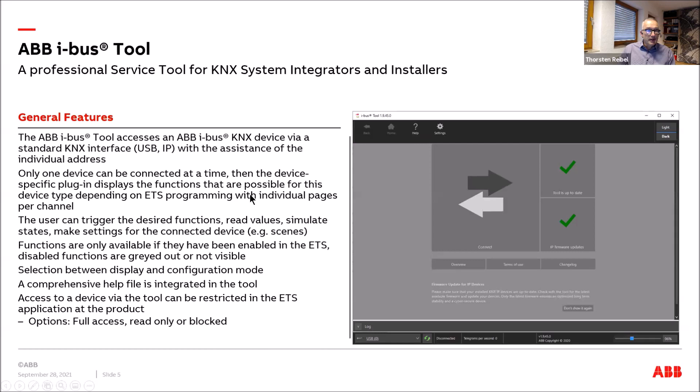From the tool you can trigger functions, read values, simulate states, and make settings — for example, store a new scene if available. These functions are only visible if they are enabled in the ETS via dynamic parameters. There are two modes: display mode, where you can only see values and actual status, and configuration mode, where you can also take action and operate functions.